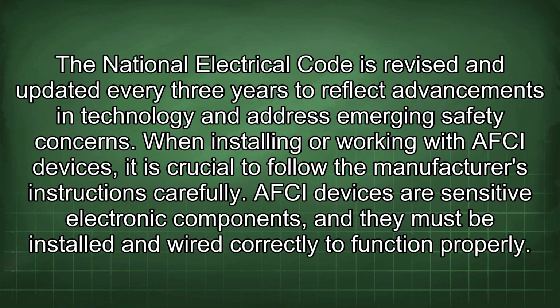The National Electrical Code is revised and updated every 3 years to reflect advancements in technology and address emerging safety concerns. When installing or working with AFCI devices, it is crucial to follow the manufacturer's instructions carefully. AFCI devices are sensitive electronic components, and they must be installed and wired correctly to function properly.